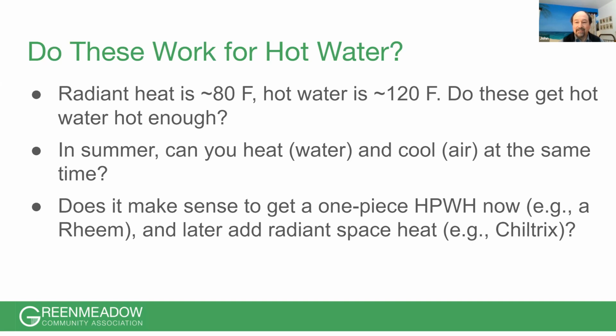I don't remember what it is at 5,500 BTUs an hour, but it's a few hours less. So what we're dealing with, for the end user, is a change in their expectation of how quickly they can have hot water back, unless we go to the backup element, which is anywhere between 13,000 and almost 16,000 BTUs, whether it's a 3.8 kW or 4.5 kW element. If we combine that with the 5.5, then we're up to 20,000 or so BTUs, which is closer to what people's expectations are of a 30,000 BTU, 70% efficient water heater. So that's still over an hour to heat it back up.